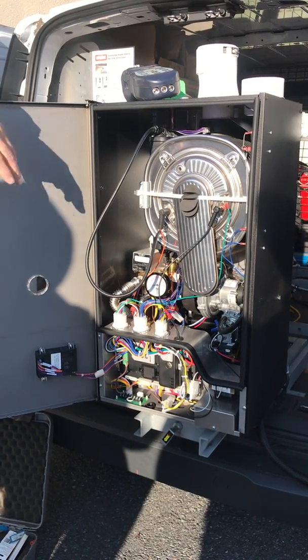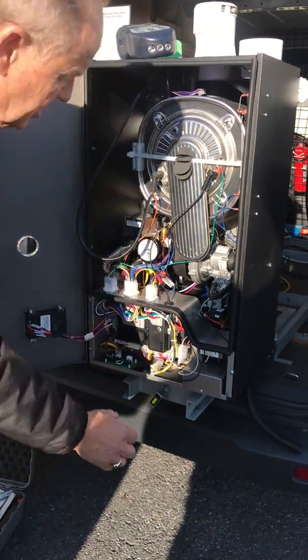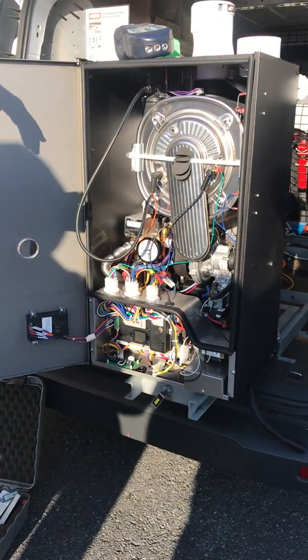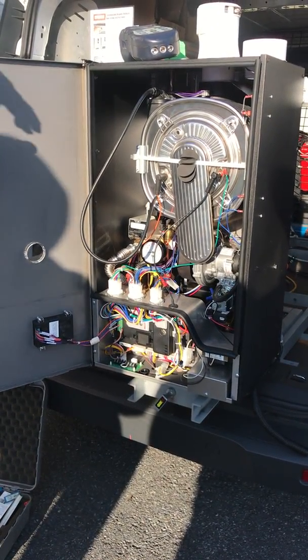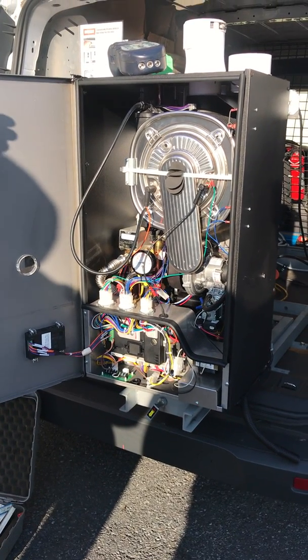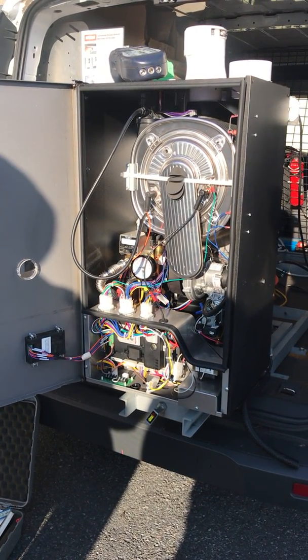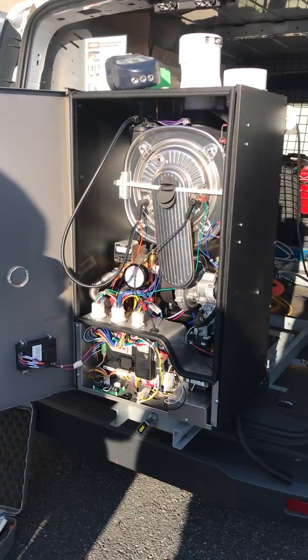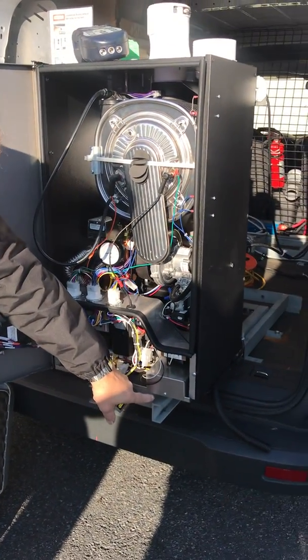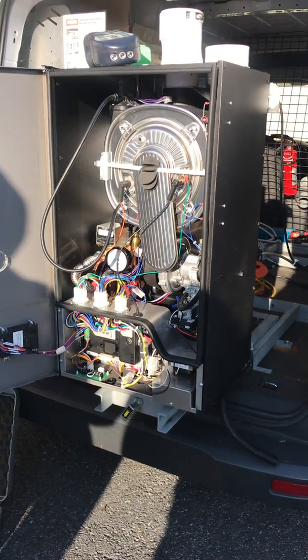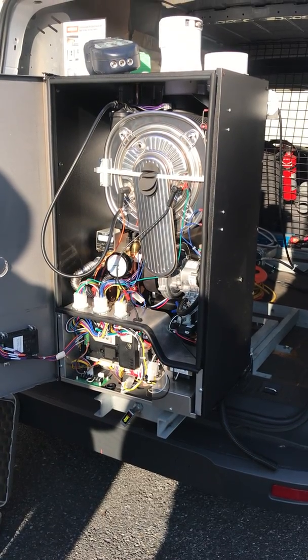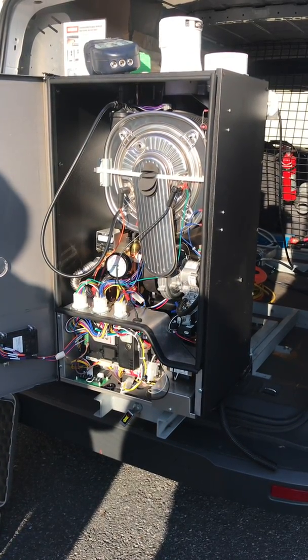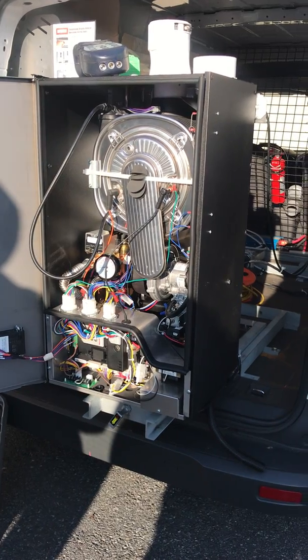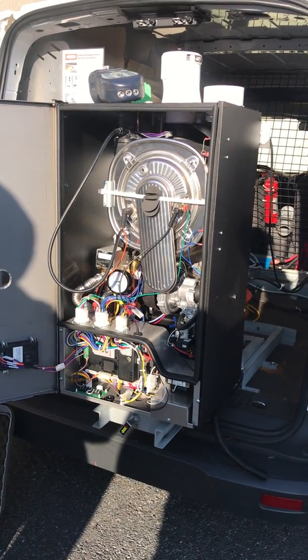Now, when you put the gas into this, your nipple's coming straight up the bottom. And what I want you to do is screw the big part of the union so it falls down. Right. So if you put it right there underneath where the gas line goes in, you then can just undo the union, shut the valve off, and now I can pull the whole gas assembly. Everything comes right straight out here. Does that make sense?